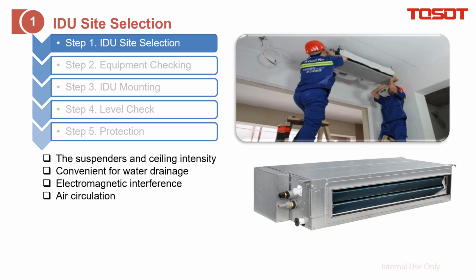The first is to select where to install this indoor unit. And here are the requirements. The first is to ensure the ceiling, or wherever you install it, is strong enough to bear the weight of this indoor unit. The next is convenience for water drainage, which means the condensing water needs to flow out, whether the indoor unit has a water pump or not. You need to consider the slope, which is long and high enough for the water drainage.